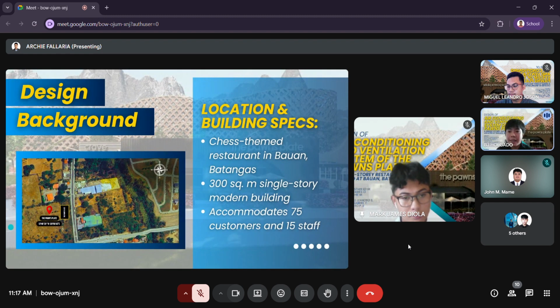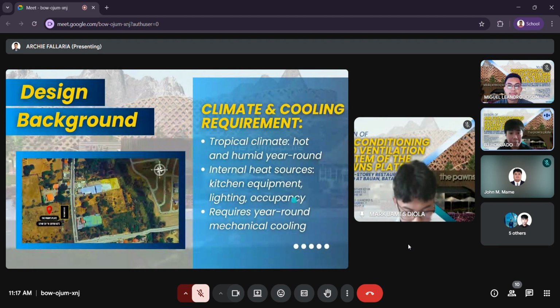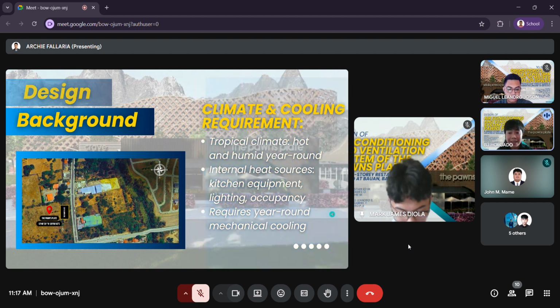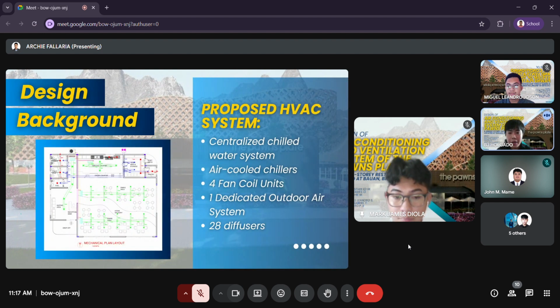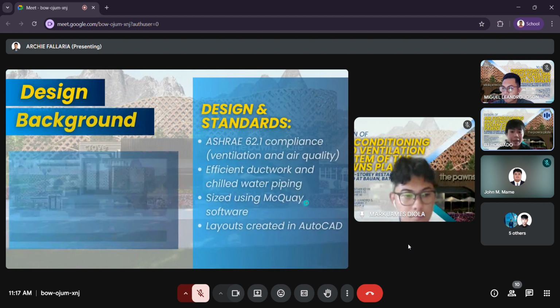The Pawns Plate, a Chess themed restaurant in Bauan, Batangas occupies a 300 square meter single story building with modern architecture and spaces for 75 customers and 15 staff. Given the local hot, humid tropical climate and internal heat from kitchen equipment, lighting, and occupancy, the restaurant requires year-round mechanical cooling. A centralized chilled water HVAC system is proposed, featuring air-cooled chillers, 4 FCUs, one DOAS unit, and 28 diffusers, designed to meet ASHRAE 62.1 standards.